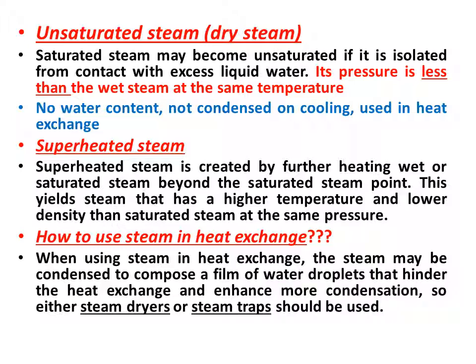How to use steam in heat exchange? When using steam in heat exchange, the steam may condense to form a film of water droplets that hinders the heat exchange and causes more condensation. So either a steam dryer or steam trap should be used.